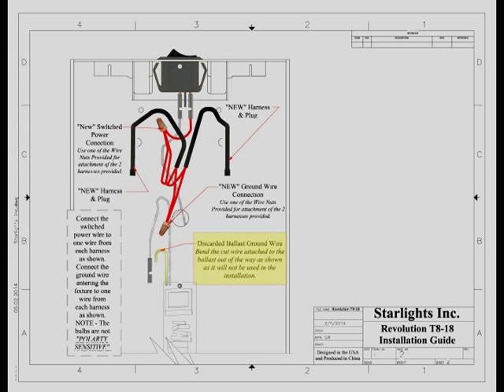Being a double tube fixture, we need to take the ground wire again and cut it. That part of the ground wire attached to the ballast, we want to bend it over as it is not going to be used. Take the other part of that wire that comes into the fixture, attach it to one wire from each of the harnesses with the wire nut provided.